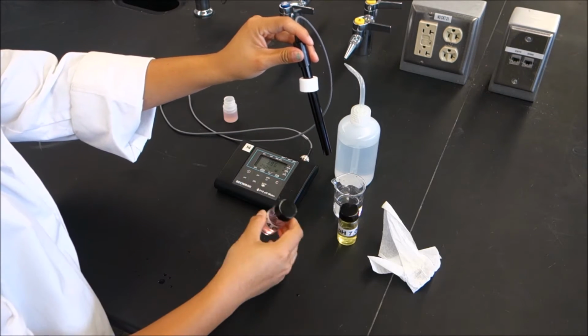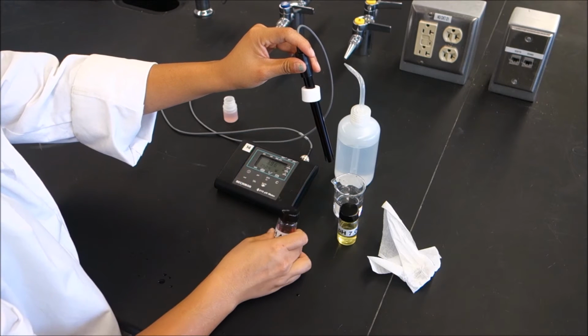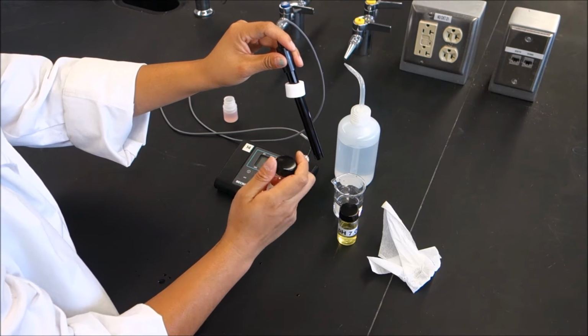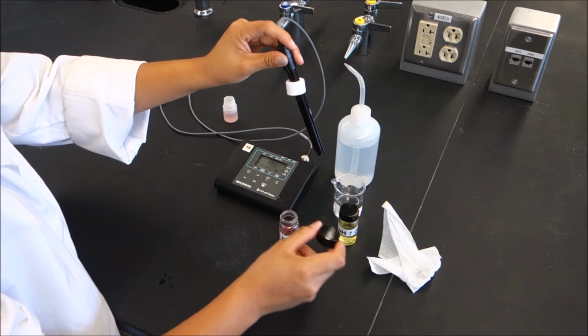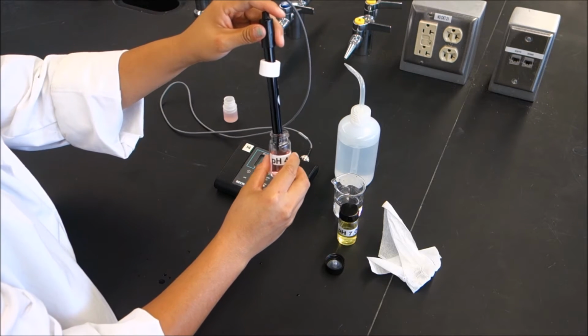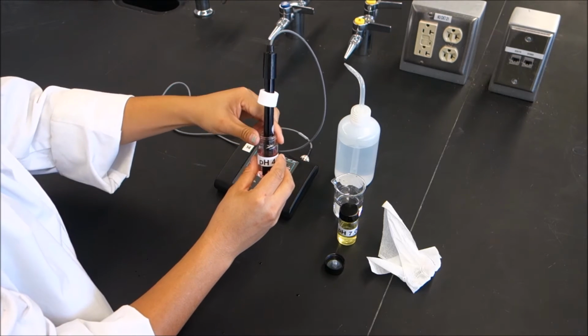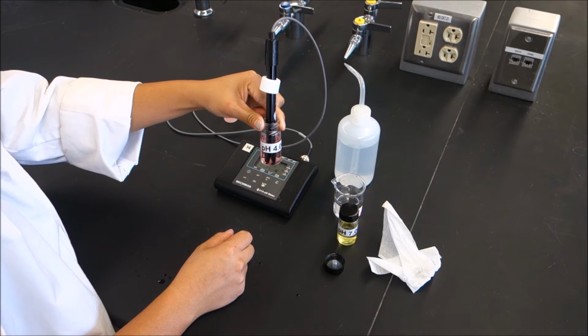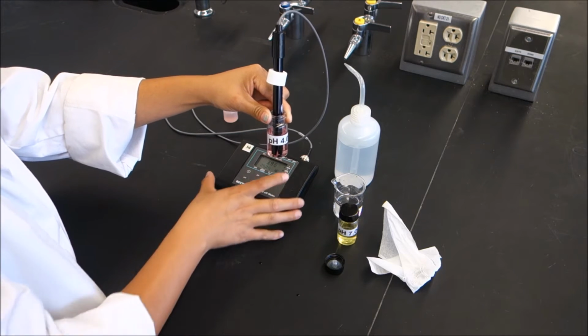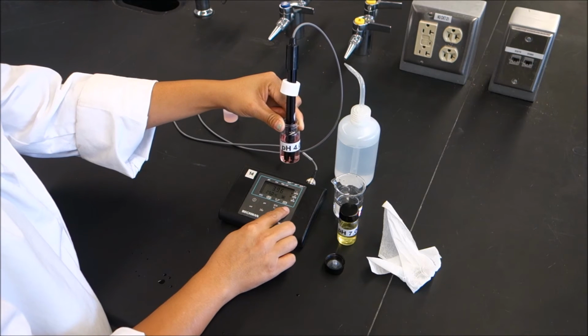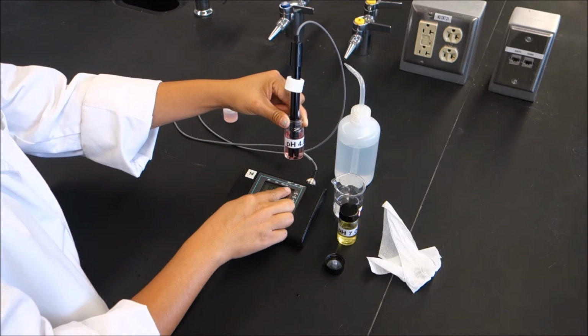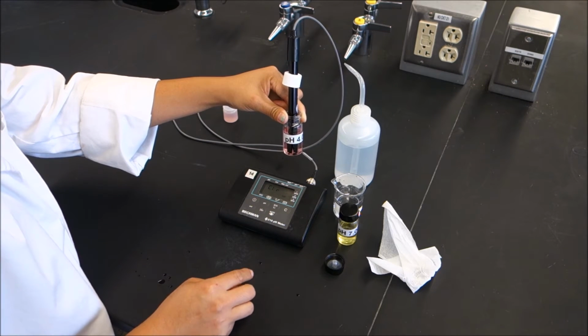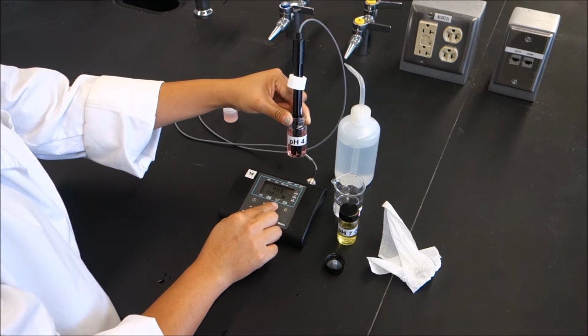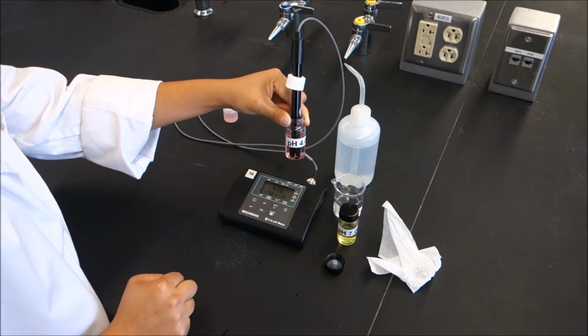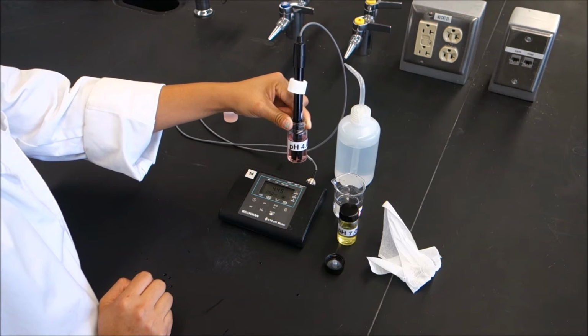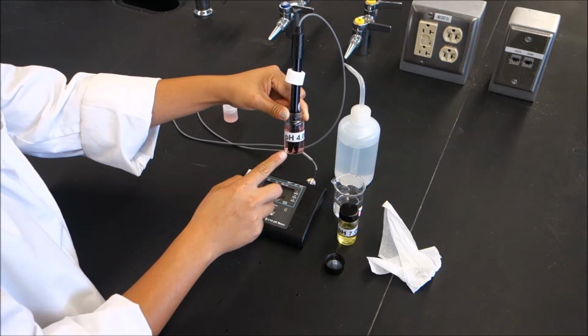First, you're going to want to calibrate it with the pH 4.0 standard. And what you're basically doing with this is telling the meter what pH this solution is. So we put it in here, let it sit for about a minute. That's close enough to a minute. So what we would do after that, we would hit clear, which clears all of the calibrations that were there before. We'd hit pH and then standard. The arrow here is going to flash and the little eyeball is going to flash until it reads that this is a pH 4.